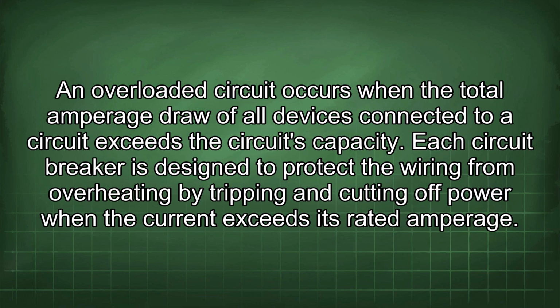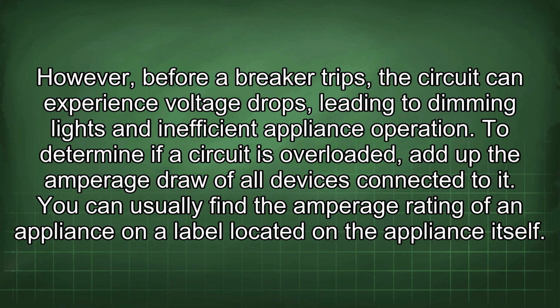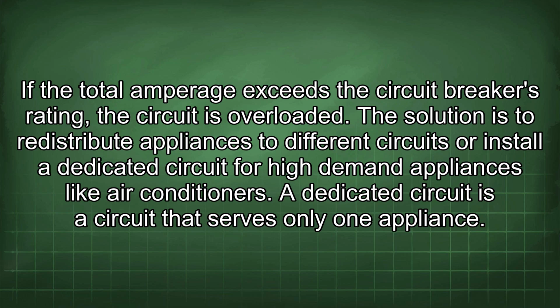An overloaded circuit occurs when the total amperage draw of all devices connected to a circuit exceeds the circuit's capacity. Each circuit breaker is designed to protect the wiring from overheating by tripping and cutting off power when the current exceeds its rated amperage. However, before a breaker trips, the circuit can experience voltage drops, leading to dimming lights and inefficient appliance operation. To determine if a circuit is overloaded, add up the amperage draw of all devices connected to it. You can usually find the amperage rating of an appliance on a label located on the appliance itself. If the total amperage exceeds the circuit breaker's rating, the circuit is overloaded.